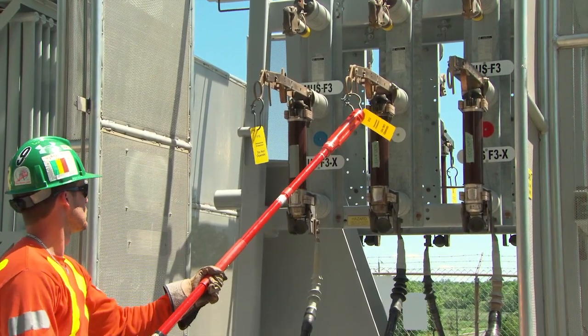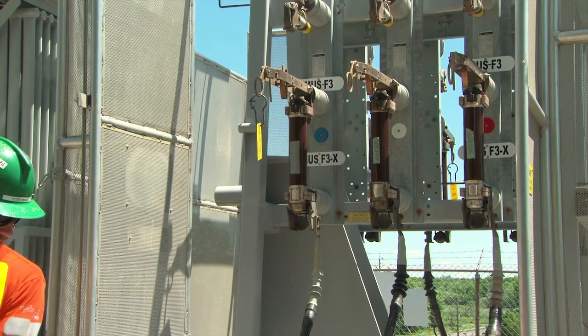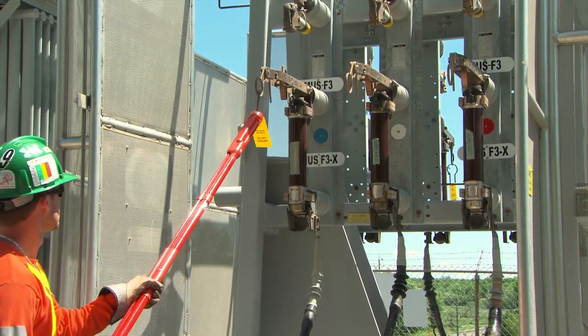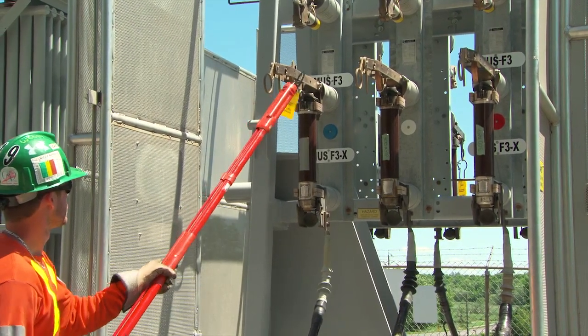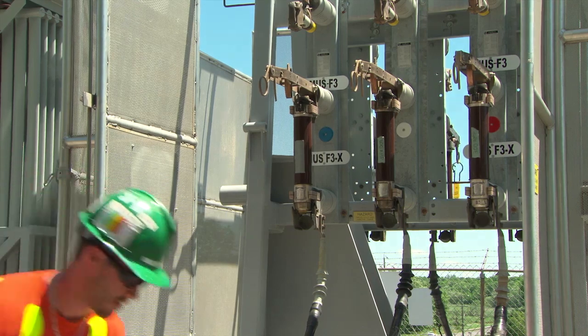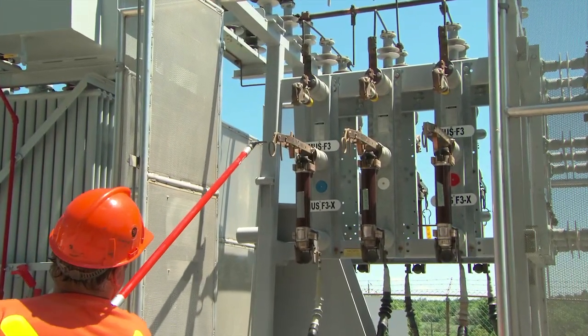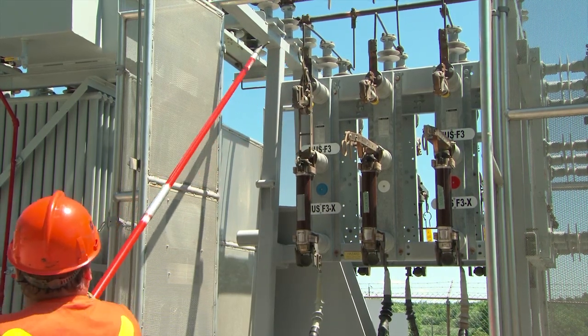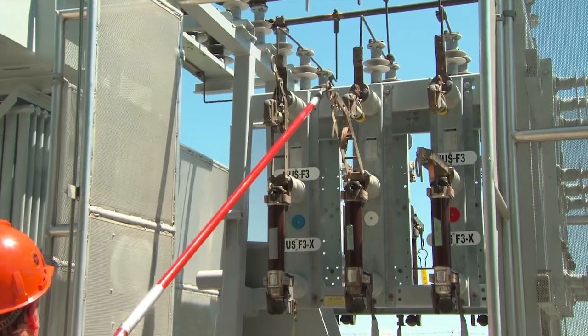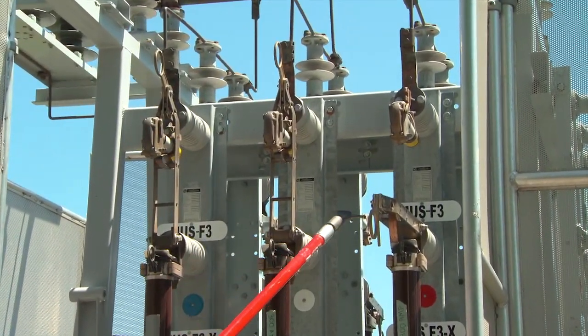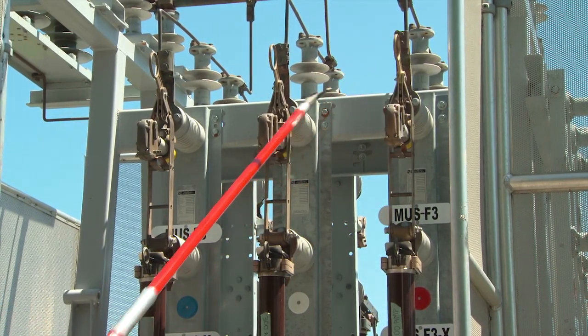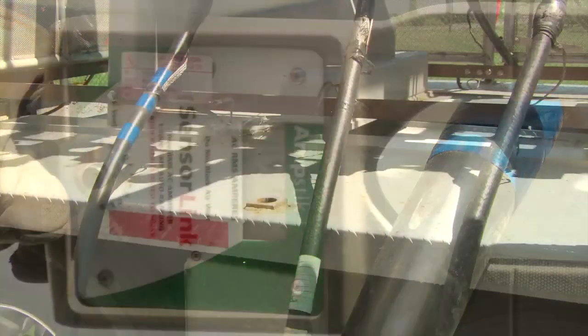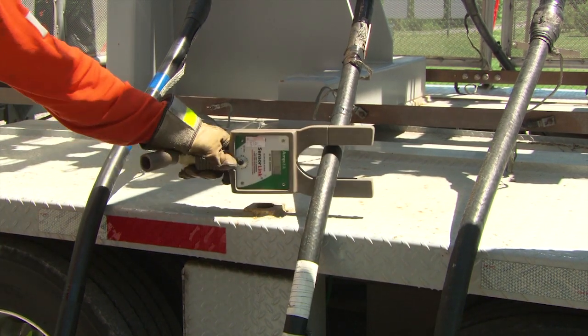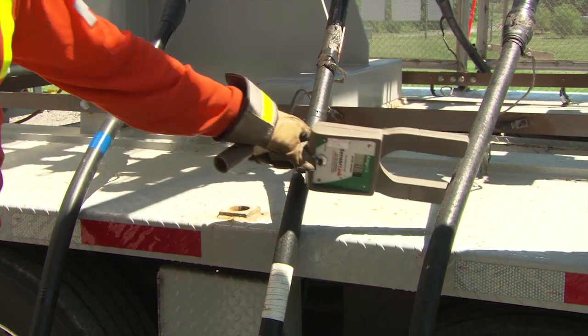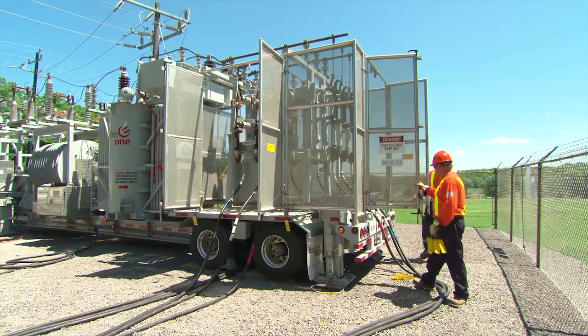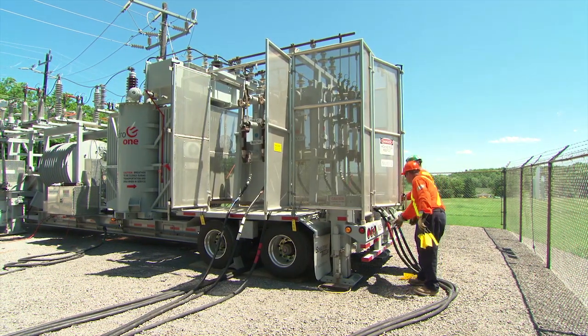Remove work protection tags on the MUS low voltage switches and close the switches. This will put the MUS and DS in parallel. Using an amp stick meter, verify current flow on the feeder cables to ensure they are carrying load. Remove the work protection tags on the feeder gates, and close and lock the gates.